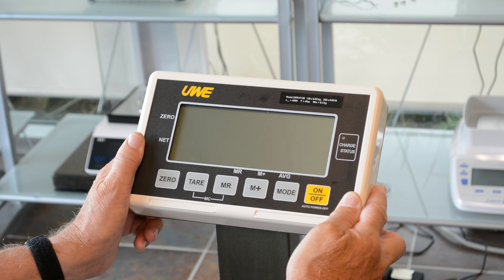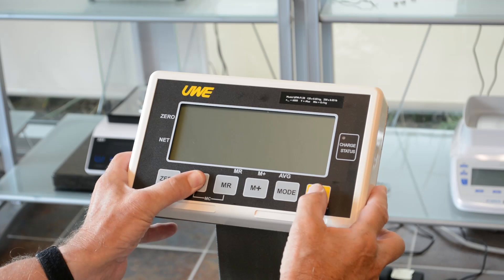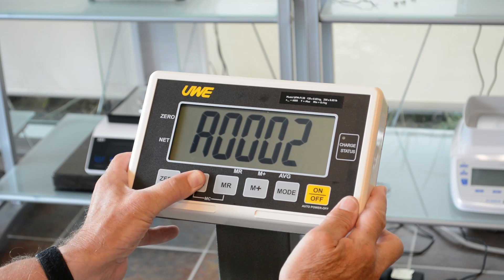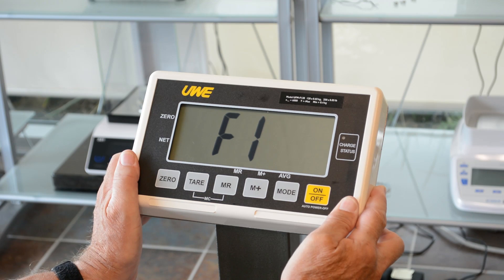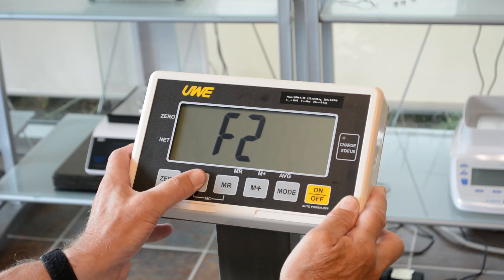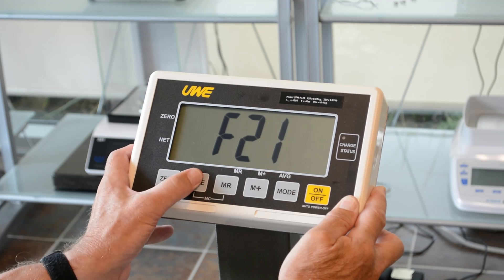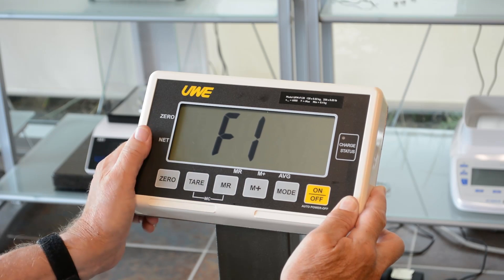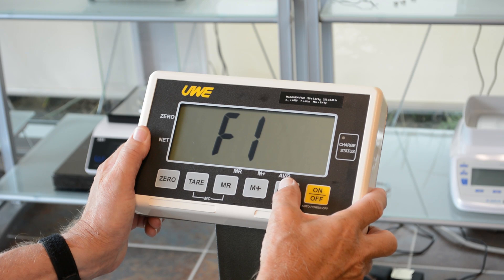The way to reset is fairly easy. You'll press and hold the tare button, turn the balance on, and wait until you read F1 before releasing your finger. If you keep your finger on the tare button, it will eventually go around the loop and come back to F1. When you're at F1, enter it by pressing the mode button.